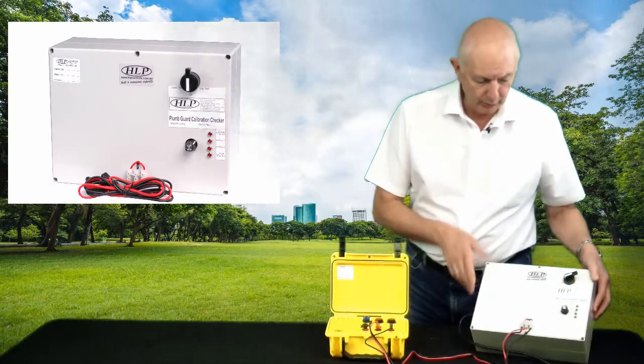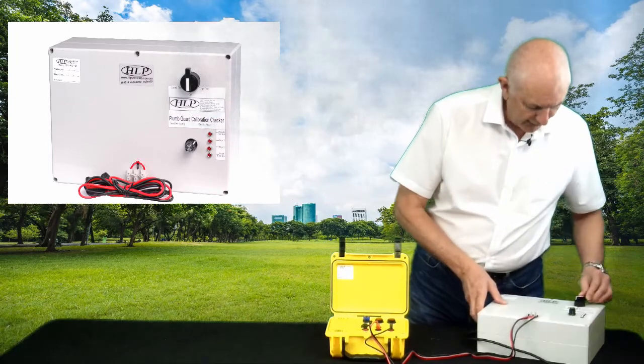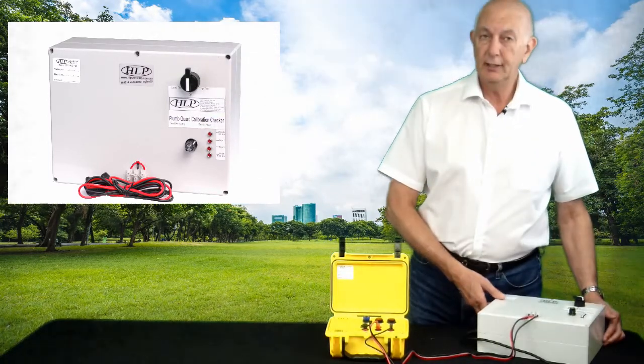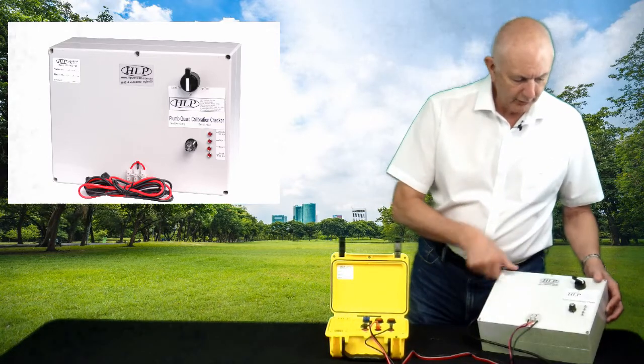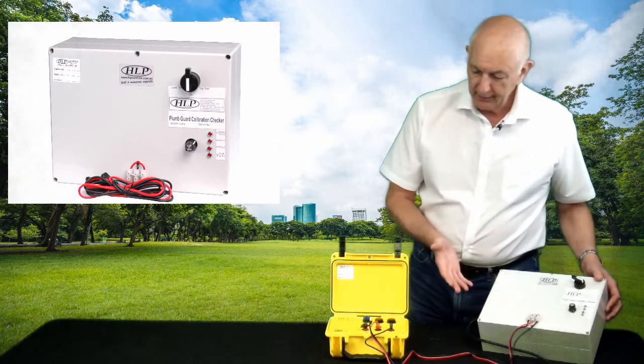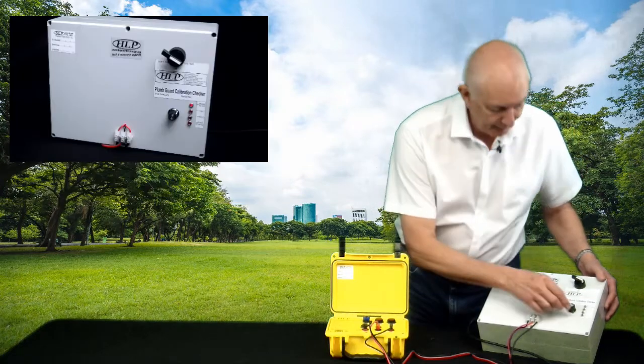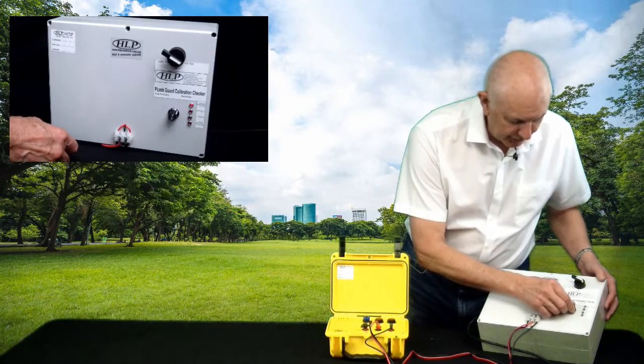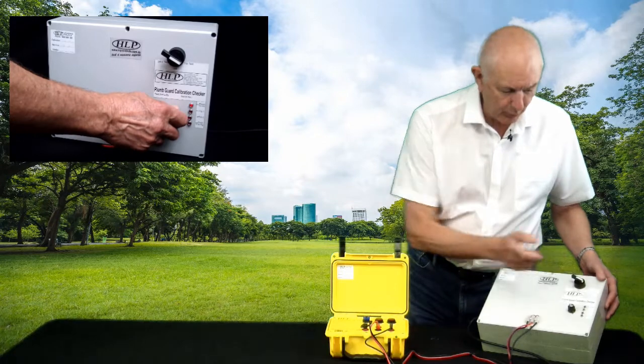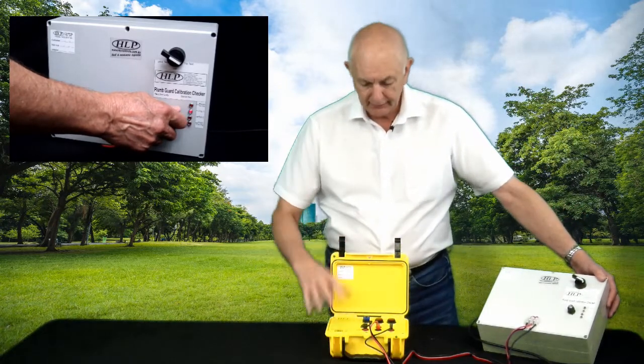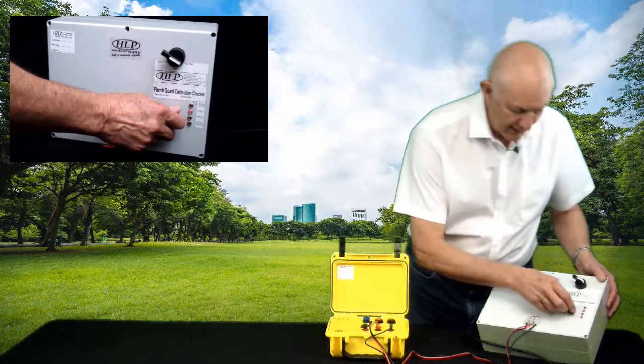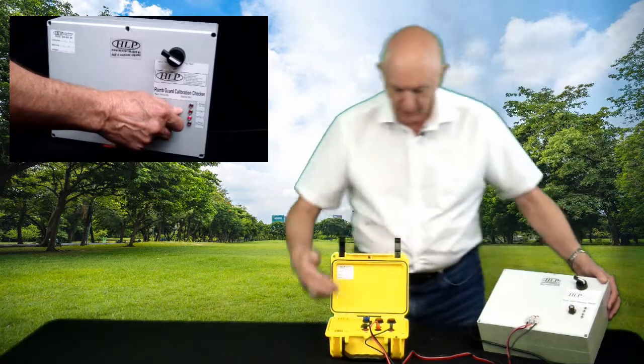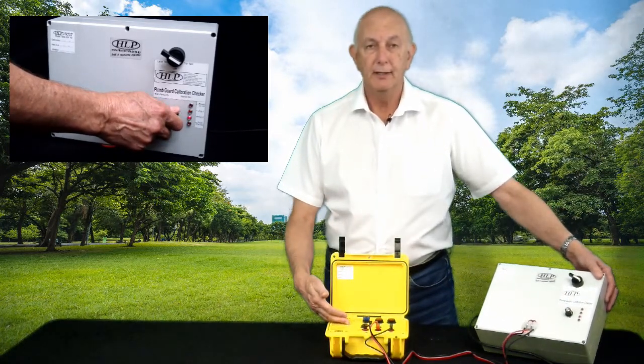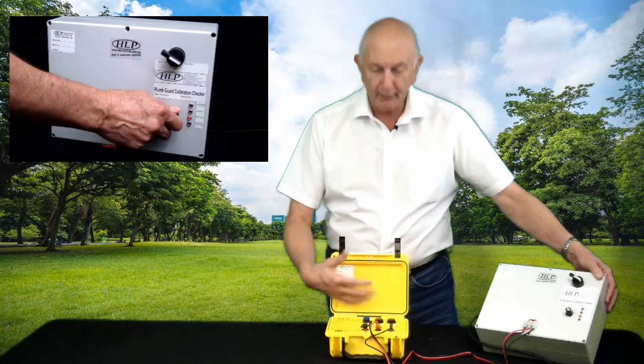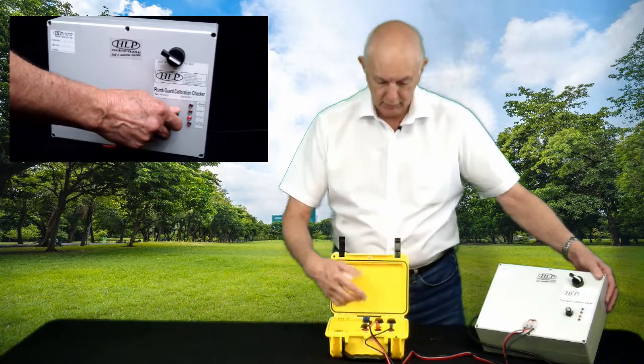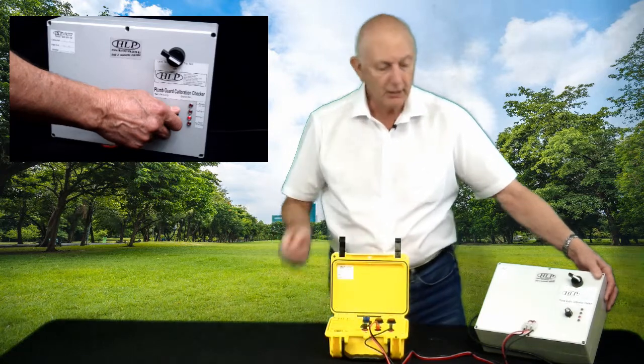So very simply, all we do with the calibration check kit is we change the switch over to trip test, and in that first position with it ready, there should be no trip of the Plumb Guard. So it's a 3-position switch. So the first position is trip 1. This Plumb Guard hasn't tripped. We go trip 2, and that trips the Plumb Guard. So that's now checked that the Plumb Guard is actually tripping at the right level. I'll turn it off so we'll stop the beeping.